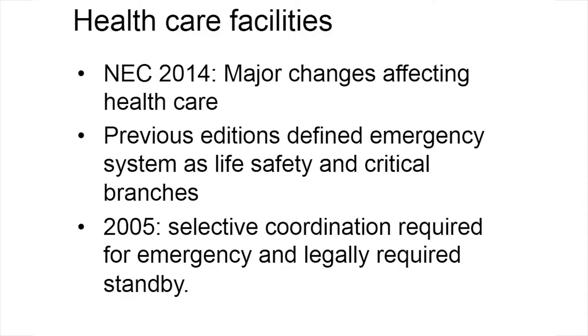And the reason for that change looks to be the stringent requirements of Articles 700 and 701 with regard to selective coordination. That requirement gets amplified with each edition of the NEC, and the writers of NFPA 99 take the view that selective coordination is just one of the considerations for an appropriate overcurrent protection system design, and too strong a commitment to selectivity could negatively impact issues like the protection function itself and the arc flash level in hospitals.